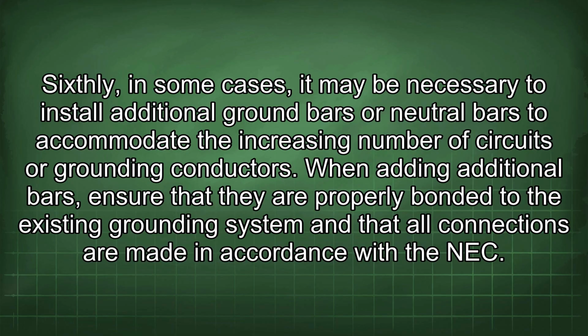Sixthly, in some cases, it may be necessary to install additional ground bars or neutral bars to accommodate the increasing number of circuits or grounding conductors. When adding additional bars, ensure that they are properly bonded to the existing grounding system and that all connections are made in accordance with the NEC.